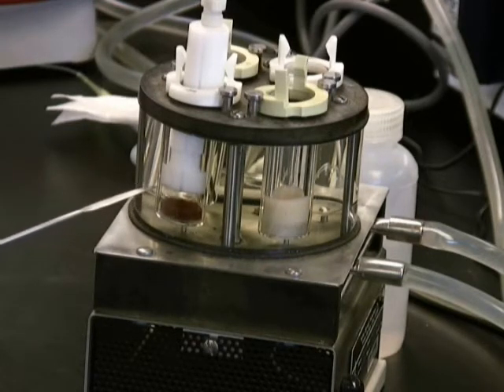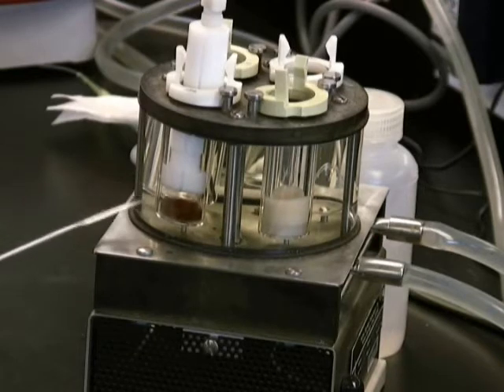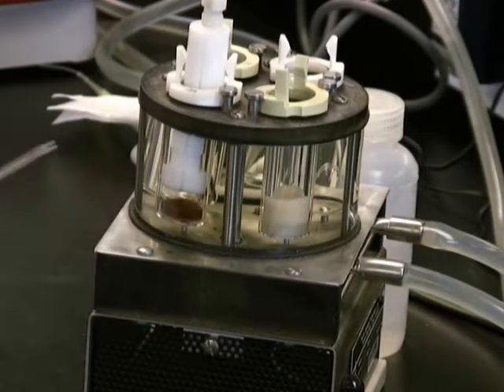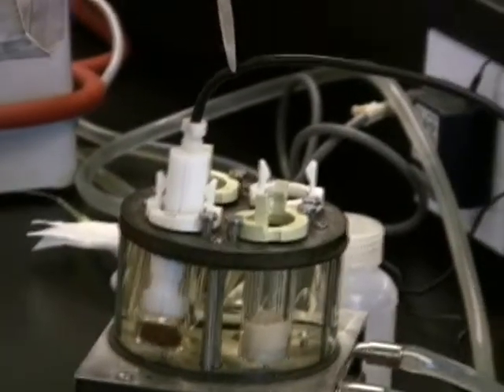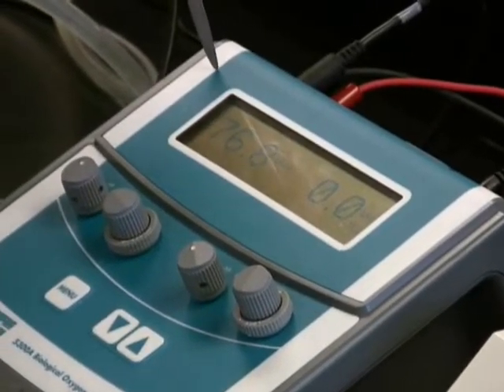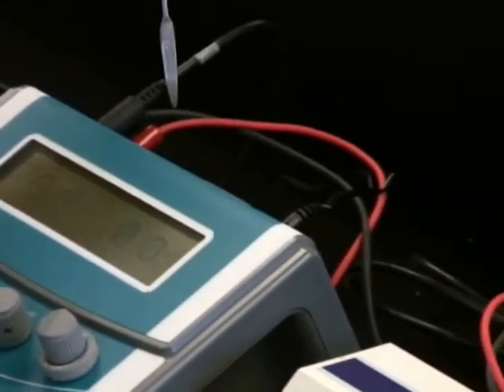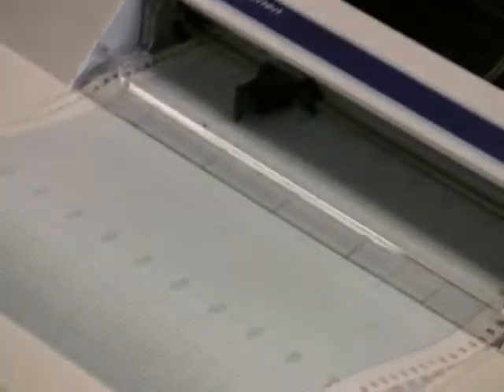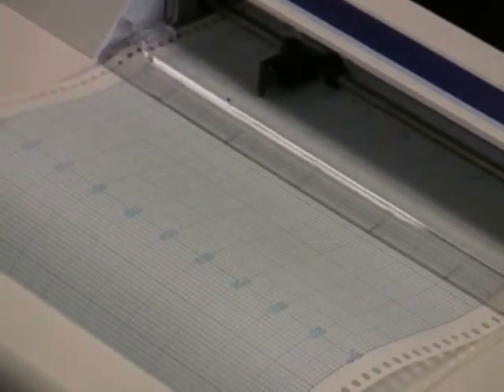So it means the oxygen that's in our buffer will start to diffuse across the membrane to reestablish the O2 concentration in the electrolyte. And within a few seconds we have a gradient established, and when we have this gradient of diffusion established, we have a constant signal that is proportional or equal to the oxygen in the buffer. Now this is a micro signal, and it travels down this lead, will come to this amplifier, will be amplified by a number of units, and then the signal will be shifted or sent to the recorder. So anything happening with the oxygen concentration will be recorded on our linear recorder.